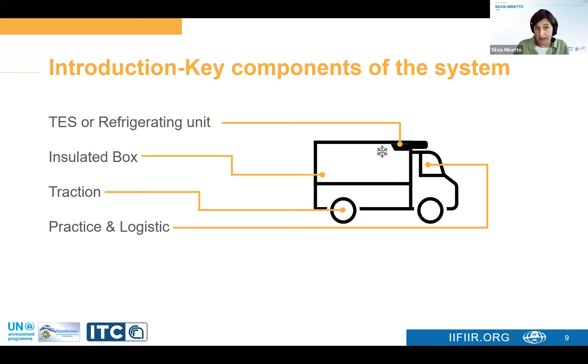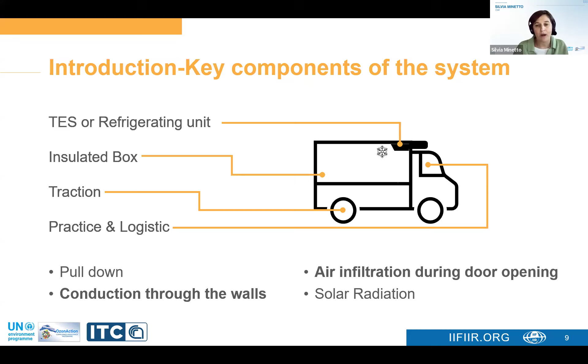There are some loads that are affecting the box, and these loads are the pull down, because we can't forget that we are within the cold chain. It means that when we load our box, we need to have already the right temperature inside, because we don't have to have fluctuations in the product temperature. And then we have conduction through the walls. We have air infiltration during door opening, because every time that we open the doors of the box, then the cold air goes out and hot and humid air comes in and replaces in a very, very short time all the air which was already cold inside the box. And then we have also solar radiation. So the first question is, what happens when temperature increases from 30 to 50?